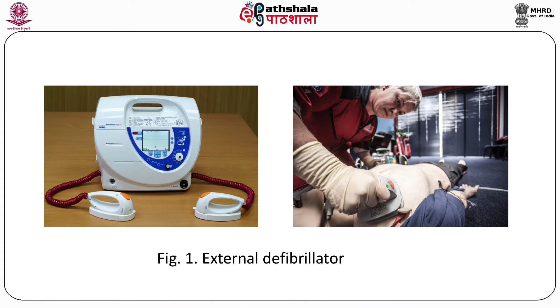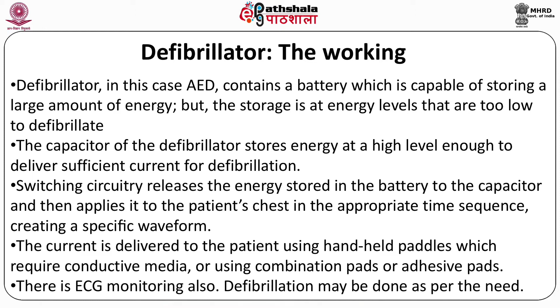Defibrillator, the working. A defibrillator, in this case an AED, contains a battery which is capable of storing a large amount of energy, but the storage is at energy levels that are too low to defibrillate. The capacitor of the defibrillator stores energy at a level high enough to deliver sufficient current for defibrillation. Switching circuitry releases the energy stored in the battery to the capacitor and then applies it to the patient's chest in the appropriate time sequence, creating a specific waveform. The current is delivered to the patient using handheld paddles which require conductive media, or using combination pads or adhesive pads. There is ECG monitoring also. Defibrillation may be done as per the need.